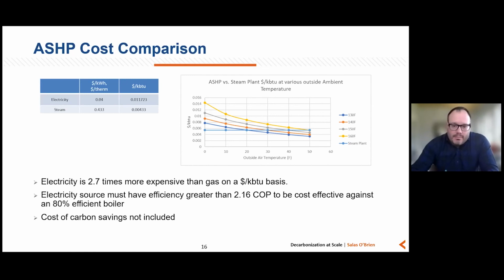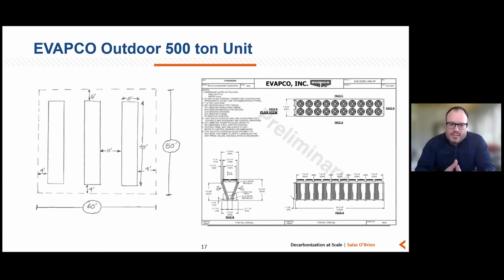And then finally, my last slide here: we think about the space challenges associated with ground source heat pumps all the time, the amount of land area that you need or how to do that underneath the building and all the other constraints associated with that. But large air source heat pumps are not small pieces of mechanical equipment either. This just gives you a sense of trying to provide enough capacity for a 500-ton system.